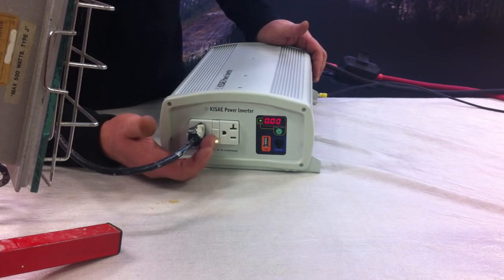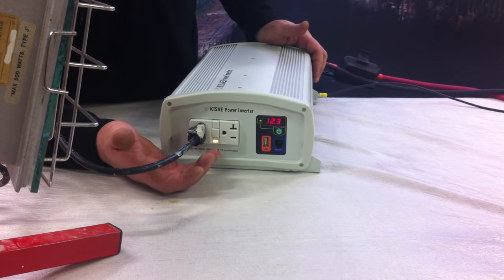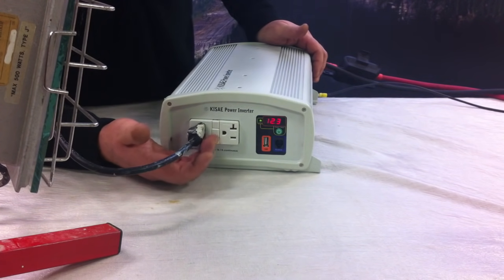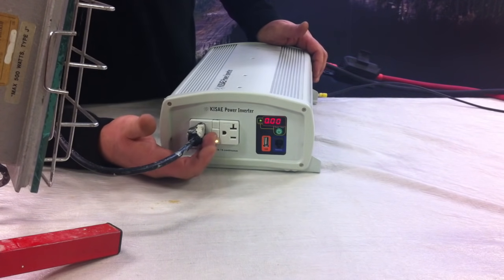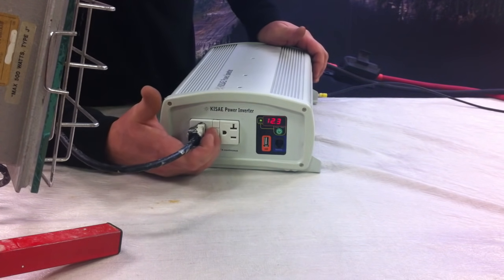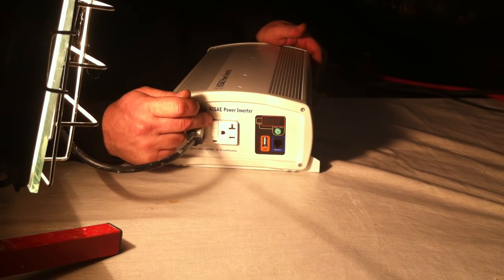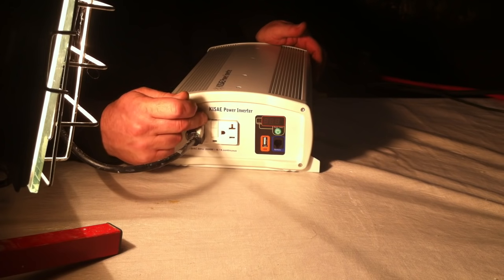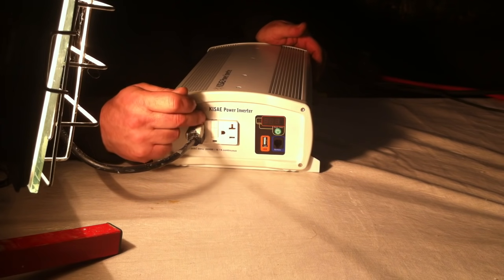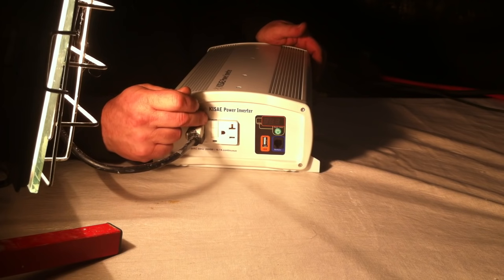One thing you want to be very cognizant of here is on warranty returns. You might get inverters back saying it doesn't work. The first thing you want to check is the GFCI. Make sure it's not tripped. In order to reset the GFCI, you have to be connected to a 12 volt source. The inverter has to be operational in order to reset the GFCI.